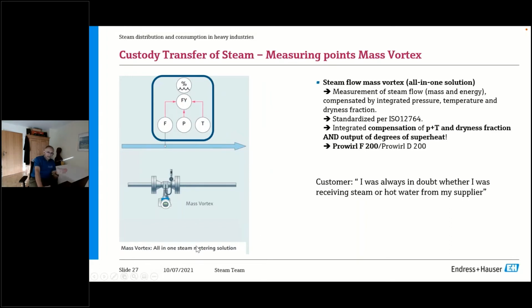Orifice plates are standardized in ISO 5167. For vortex meters, there's also a standard available since 2017. I was on the standard committee. That's ISO 12764. And our vortex meter is, of course, complying with that standard. I recommend for custody transfer of steam to use our vortex meter with integrated pressure and temperature and the dryness fraction. Why? Because only if you know the dryness fraction and you have steam that is actually at the saturation line, only then will you know if you're charging or getting charged for hot water or for steam.